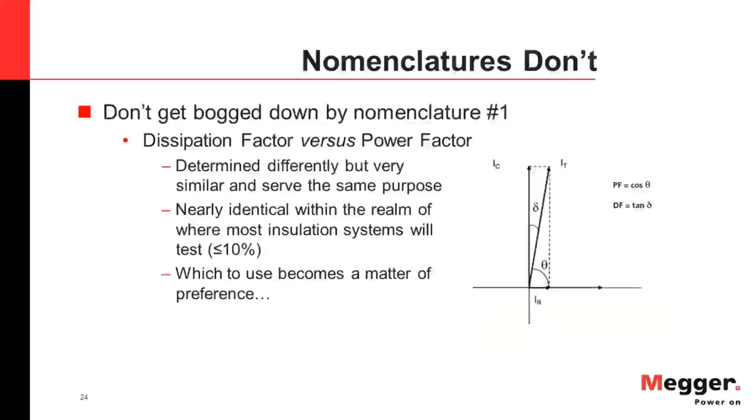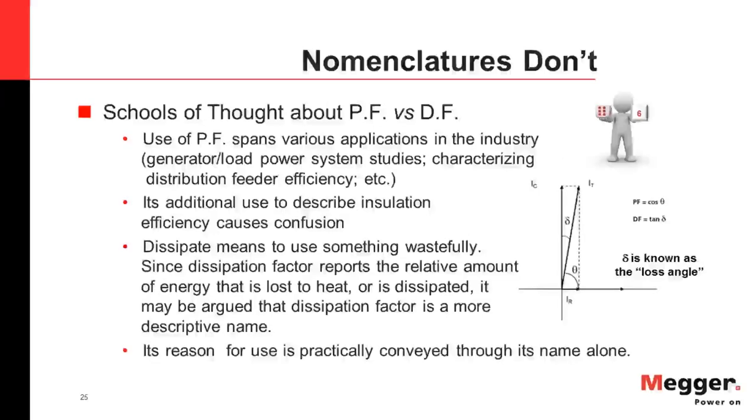But just to give you maybe some schools of thought about power factor versus dissipation factor. The use of power factor spans various applications in our industry, and in fact is often more readily associated with its other uses, like in performing power system studies or characterizing distribution feeder efficiency. So some feel that its additional use to now describe insulation efficiency may cause confusion. In fact, I hear a lot from power plant personnel, as one example, who are really less than enthused about the use of power factor for insulation assessment.